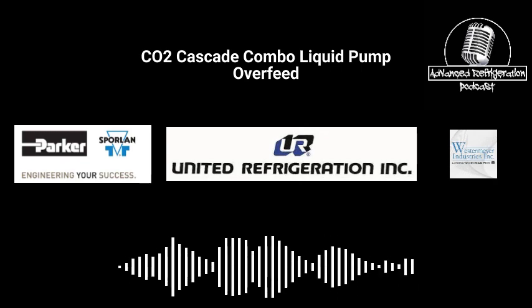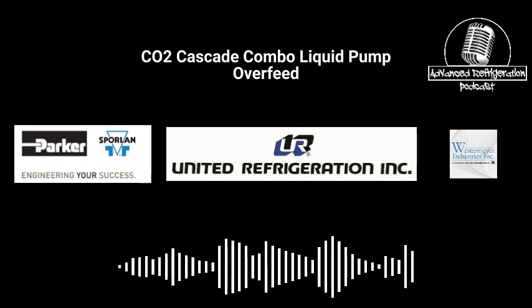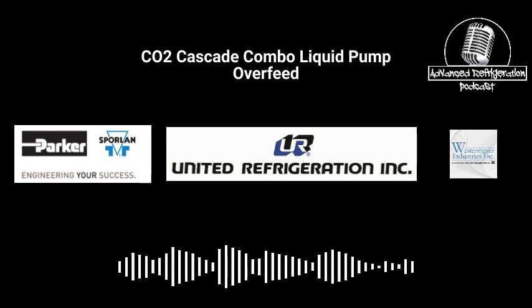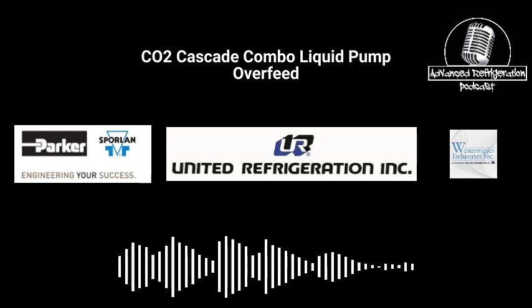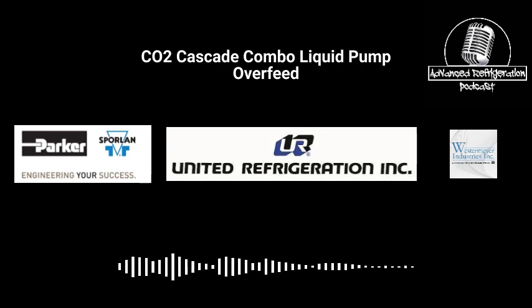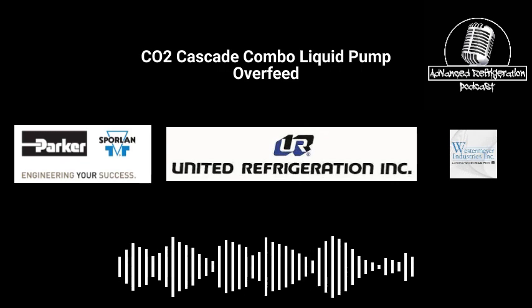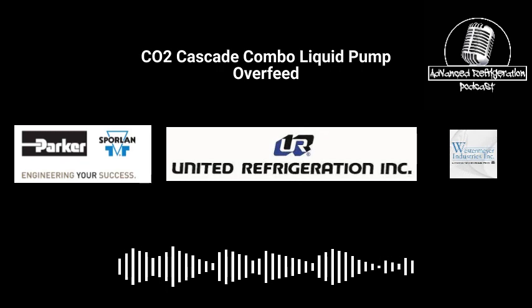So, I call it below freezing defrost, because that's what it is. Well, that's why I was curious. You get a little bit of discharge superheat, but not that much. Some of these units also, by the way, have an auxiliary condenser. It's basically used so if the power goes out, that auxiliary condenser working off a generator can bring the pressure down below the relief, so it doesn't pop the relief.